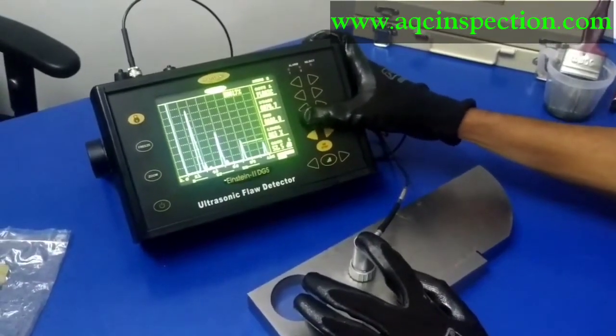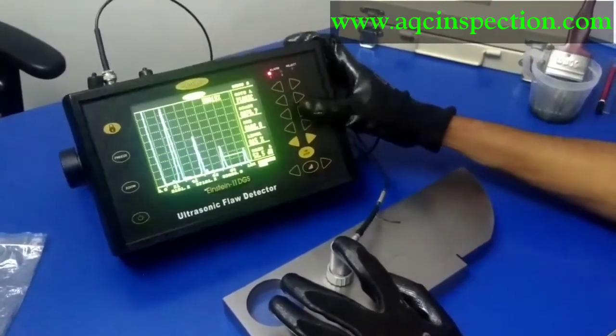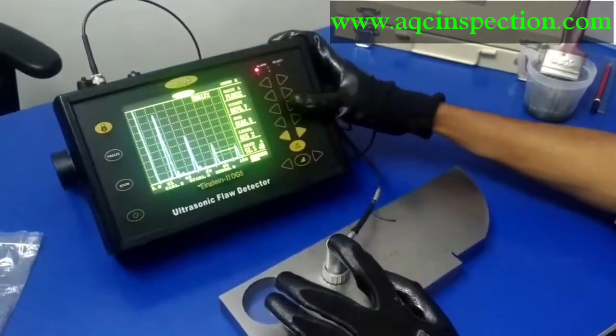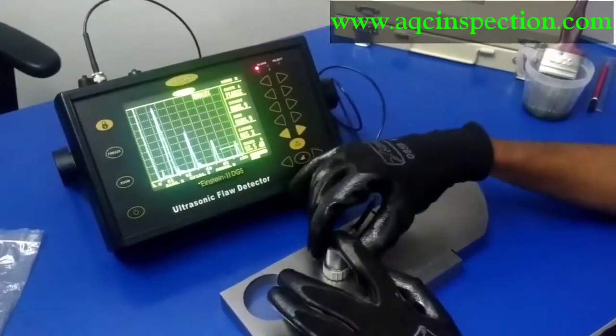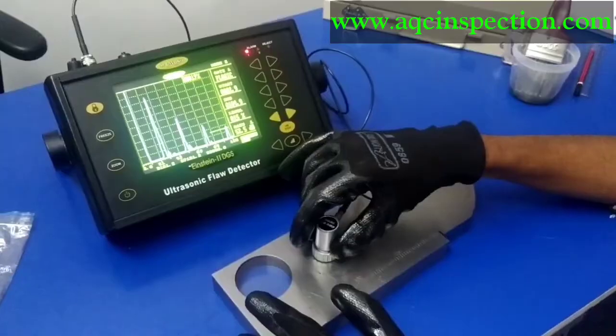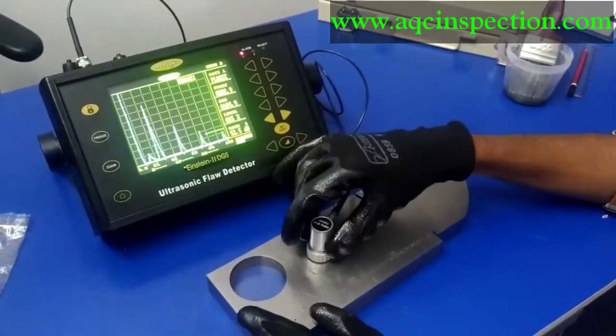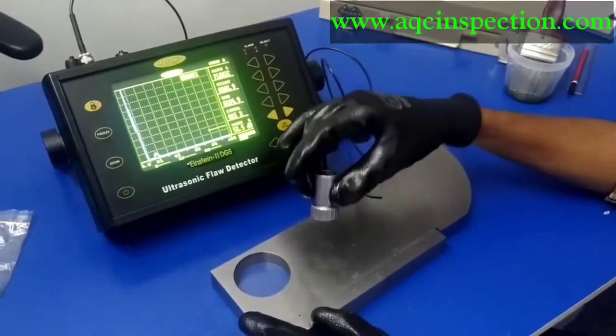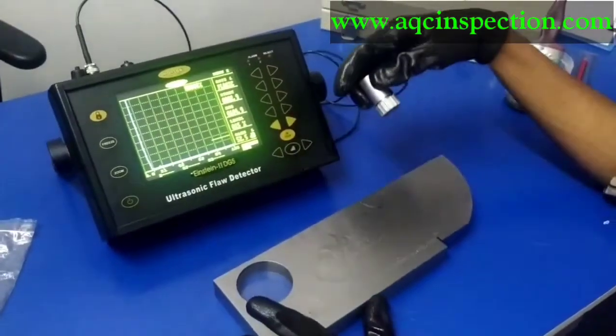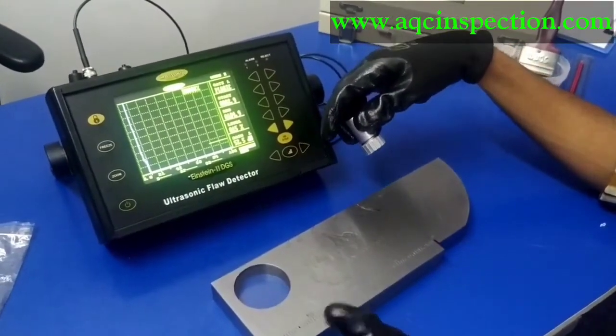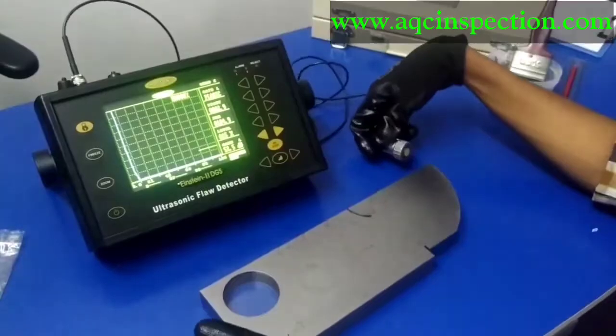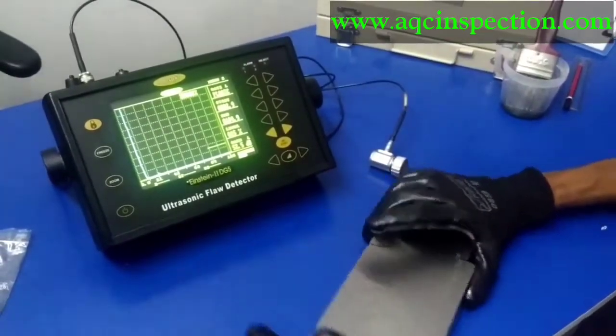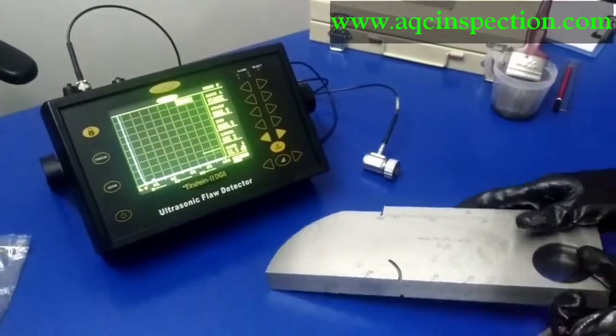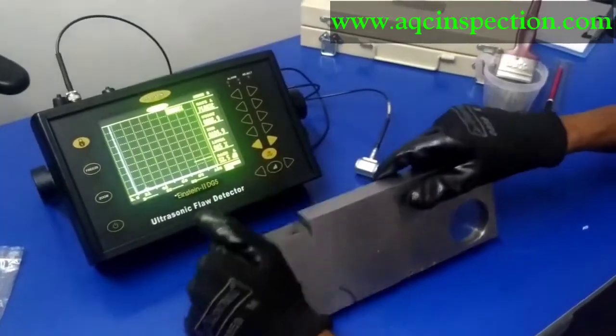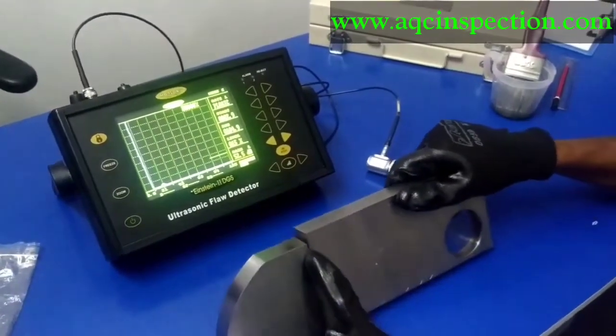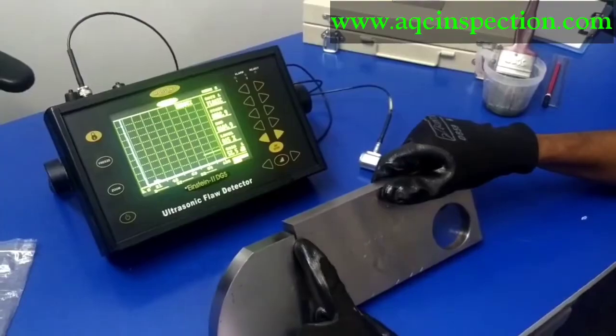So I'm going to reduce the level right here. See, it is showing as 101.2. That's okay. This is the normal calibration using a V1 block, but there are several steps to it, like checking the vertical linearity, resolution, sensitivity, and so on. So let me do the resolution check right now, which is, as you can see, this is the notch right here, 5 mm gap.